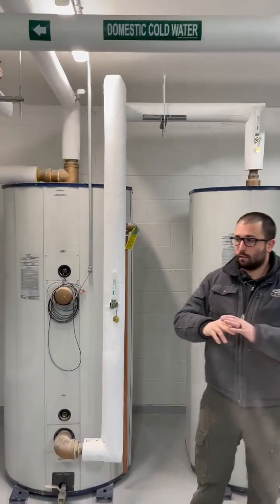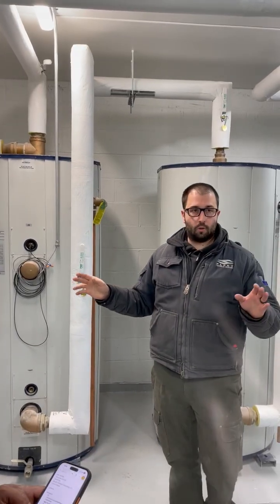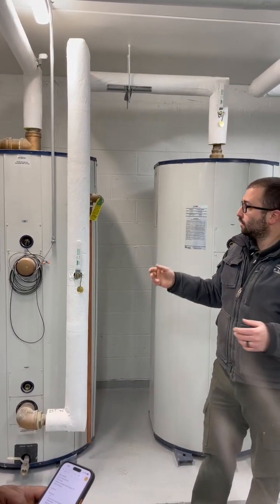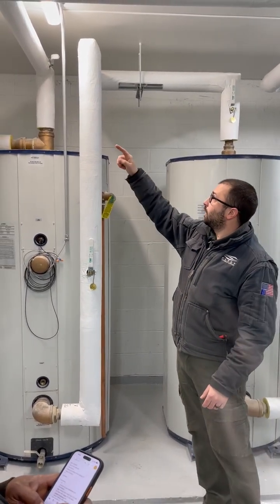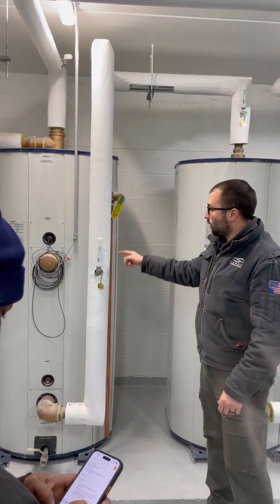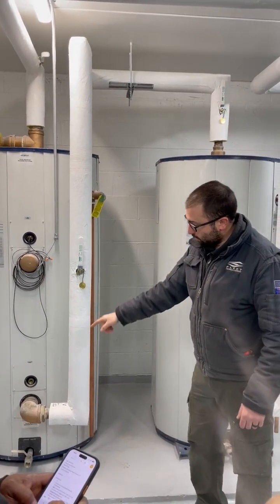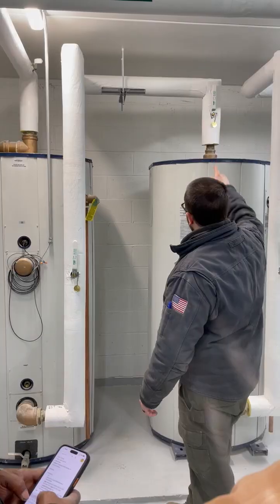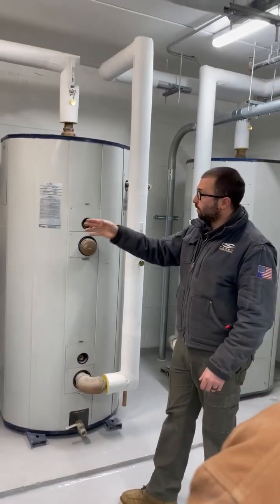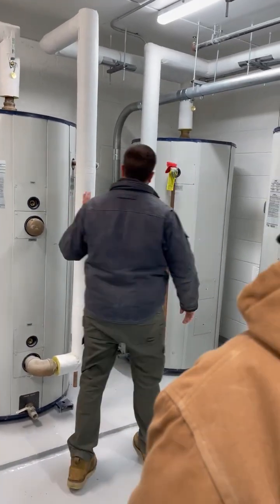Now, let's pretend the building's not using any hot water, we're in what we call a recharge. So in a recharge situation, 170 degrees coming into this tank, it's going to keep filling this tank all the way down. It's going to come up and go into the next one. So this is a series circuit. They're all in line with each other. So we're going to keep charging these tanks all the way down.